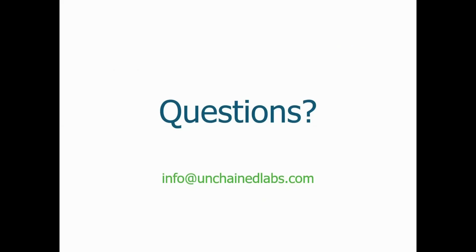All right. One more question for you. Can you use a Uni for several tests? Thanks for that one. As I was saying earlier in response to Jennifer's question, the Uni in itself is a single-use item, but that is on a per cuvette basis. So of the 16, if you use some today and some tomorrow, that is fine, but the cuvette itself is designed for single use. However, this is a kind of a flexible question to ask, is it several data points? Because in an experiment where you record DLS, SLS, and fluorescence, you get several data points out of it. So yes, the Uni can be used for several data points, but one quartz cuvette is a single-use item.